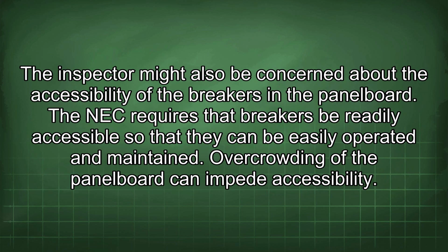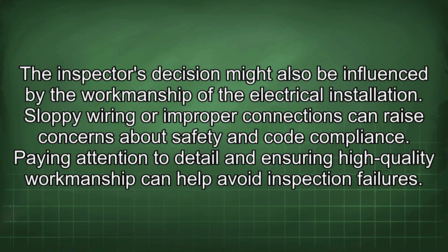The inspector might also be concerned about the accessibility of the breakers in the panel board. The NEC requires that breakers be readily accessible so that they can be easily operated and maintained. Overcrowding of the panel board can impede accessibility. The inspector's decision might also be influenced by the workmanship of the electrical installation. Sloppy wiring or improper connections can raise concerns about safety and code compliance. Paying attention to detail and ensuring high-quality workmanship can help avoid inspection failures.